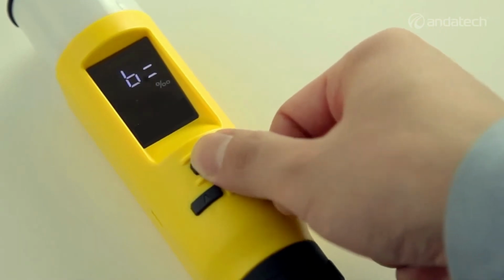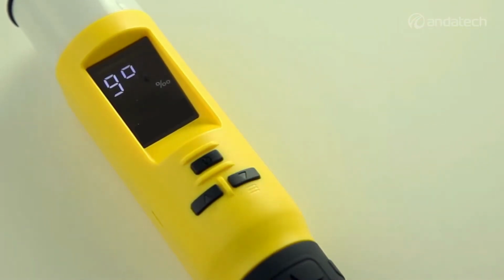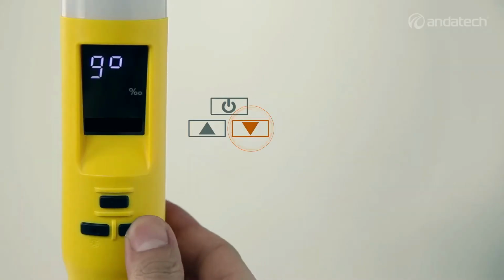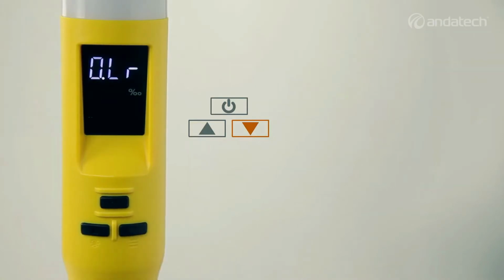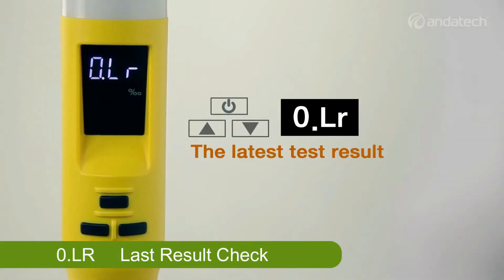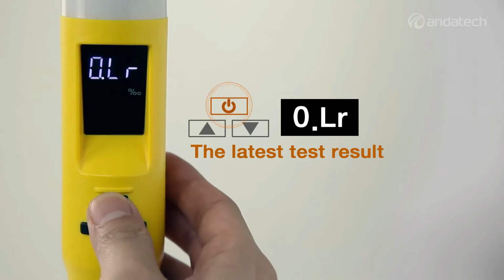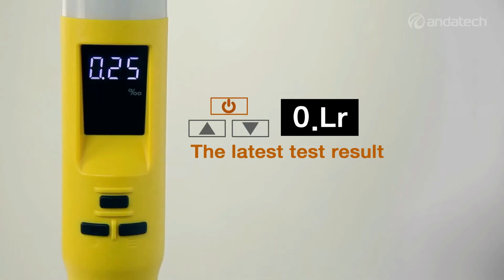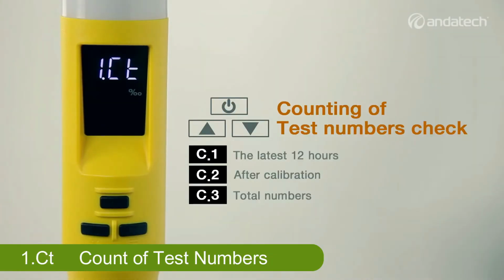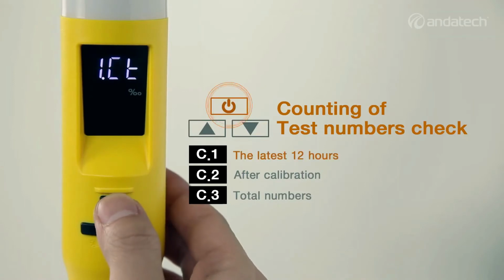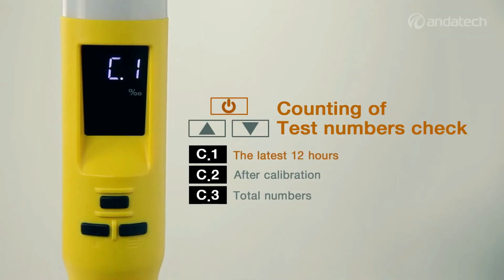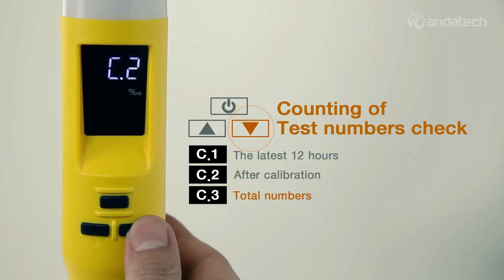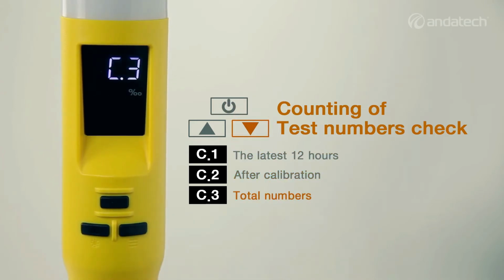The Sentry's menu is displayed when the down button, located below the power button, is pressed and held down. The first mode, OLR, is a menu showing the latest test result, and displays the most recent result. 1CT is the mode that displays the number of tests conducted and shows 3 types. C1 is the number of tests conducted in the past 12 hours. C2 indicates the tests after calibration. And C3 is the total number of tests carried out.